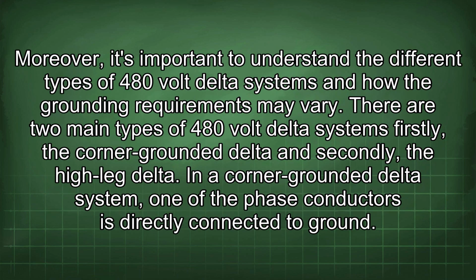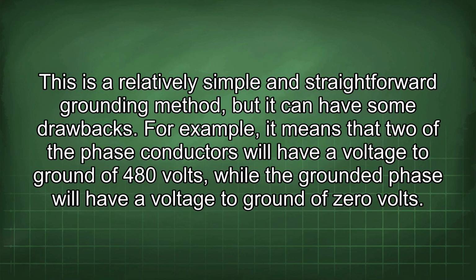Moreover, it's important to understand the different types of 480-volt delta systems and how the grounding requirements may vary. There are two main types of 480-volt delta systems: firstly, the corner-grounded delta, and secondly, the high-leg delta. In a corner-grounded delta system, one of the phase conductors is directly connected to ground. This is a relatively simple and straightforward grounding method, but it can have some drawbacks. For example, it means that two of the phase conductors will have a voltage to ground of 480 volts, while the grounded phase will have a voltage to ground of 0 volts.